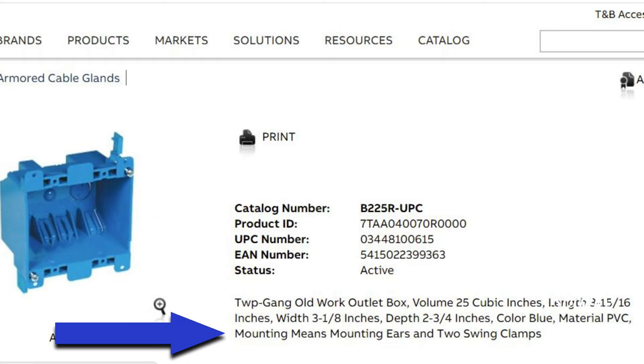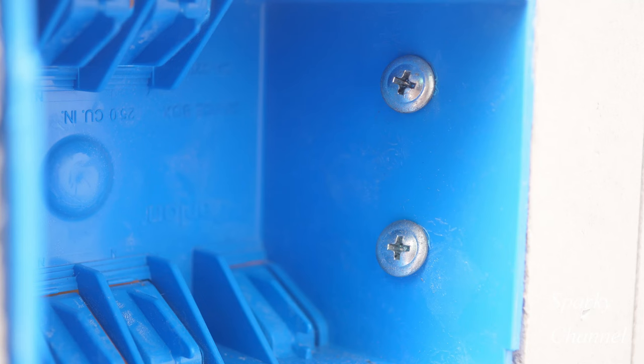So I'm going to come down on the side of saying that those two screws, even though they're well meaning, are not allowed by the 2020 NEC. Also I think those screws could cause a possible shorting hazard. I understand that some inspectors and some authorities having jurisdiction are going to say this is okay to put in those screws. I think that if you go strictly by the NEC, it's not legal.